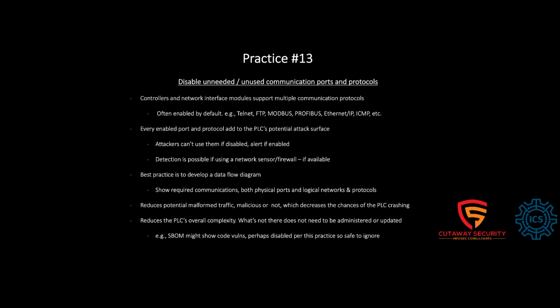Next up, another one. This is disable unneeded or unused communication ports and protocols. So historically, we've known that controllers, many of them are backward compatible. They're supporting many kinds of protocols. But unfortunately, these protocols are enabled by default on a lot of these PLCs. So this practice says, disable them if you're not using them, right? Because every enabled port or protocol adds to the PLC's attack surface. And if it's not enabled, then the attackers can't use them.